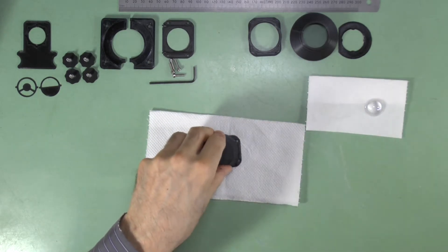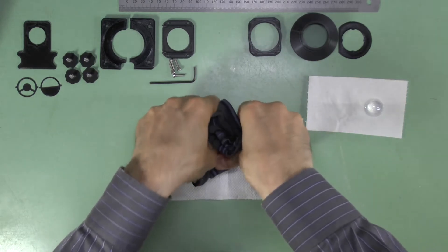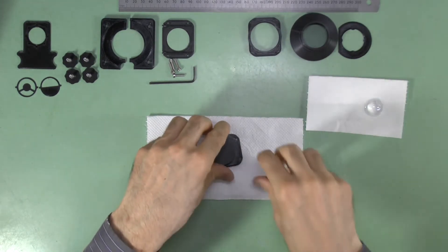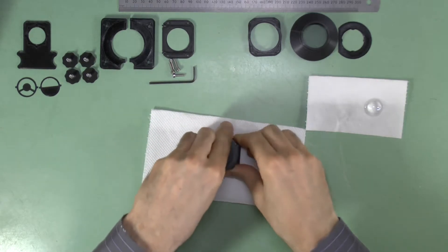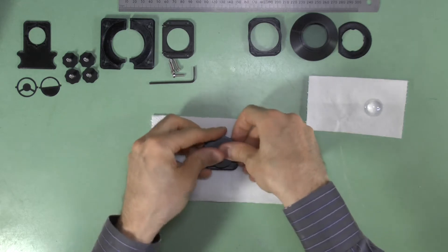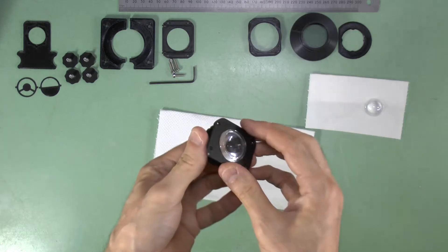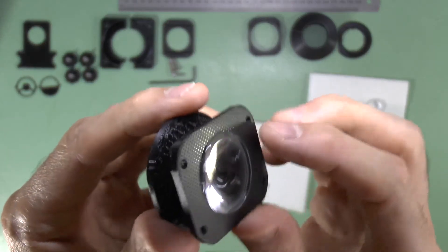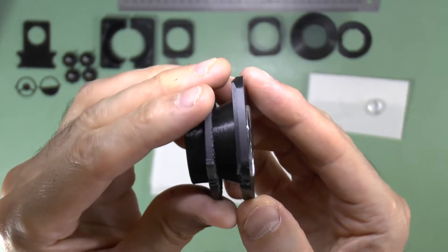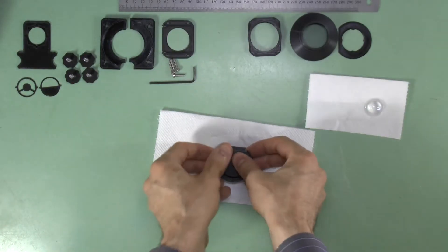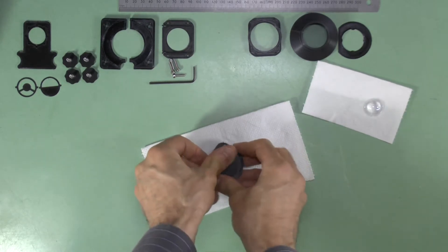You may need to use some padding on top to prevent hurting yourself due to the pressure. Note that the 30mm lens will only go part way into the recess. About half a millimeter will stand proud of the lens holder surface. Check that an equal amount of lens glass protrudes all around the circumference and, if it is not even, lay the assembly flat and apply directed pressure to the more proud part to even it out. If this doesn't work, remove the lens and start again.